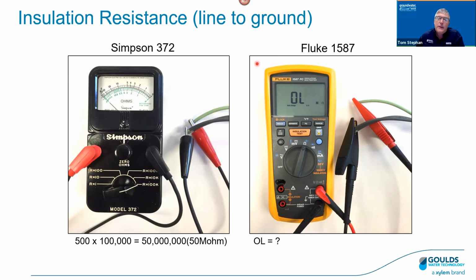So let's take another look. If I do that same exact test using a Fluke 1587, which is what we happen to use at the schools, and I'm just going to use the ohm meter, all right? Well, I do the same test. I've got the same motor, and I get an OL. Well, OL means that it's an open lead. You have no connection, no continuity between the hot leads and the ground. Again, it's showing that that's good, that there's no issue, right? But it's a little different.